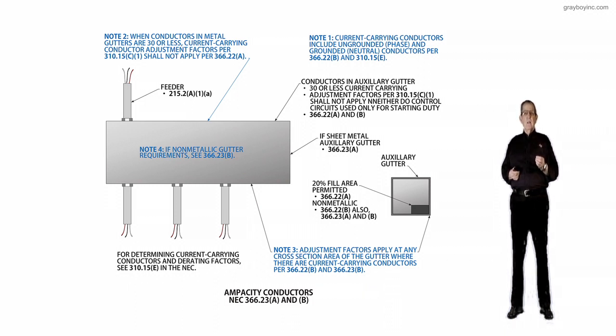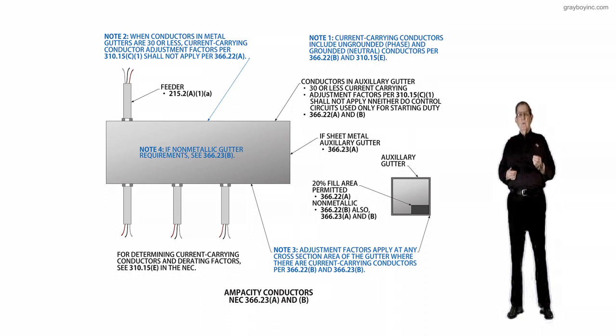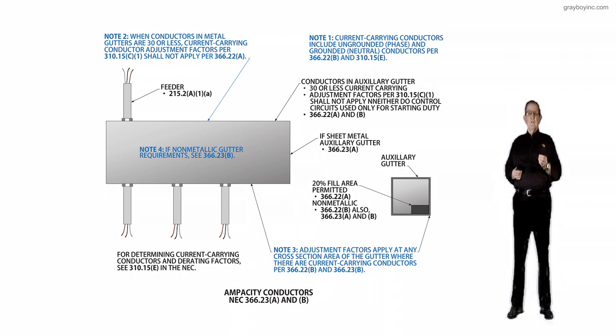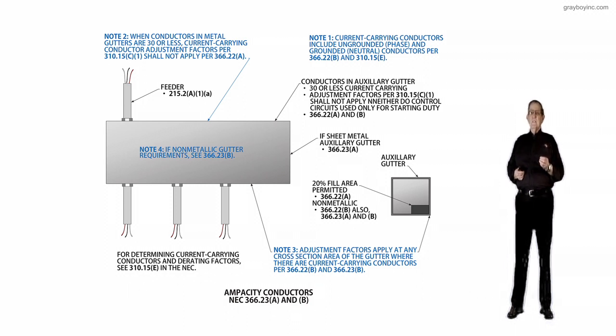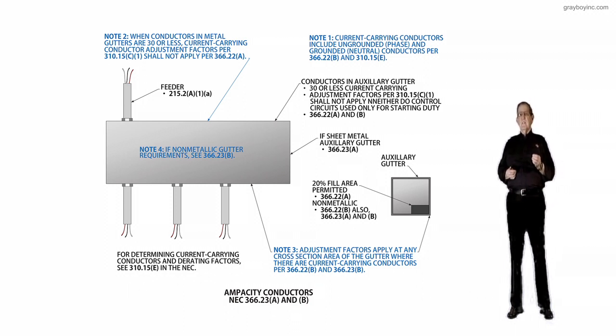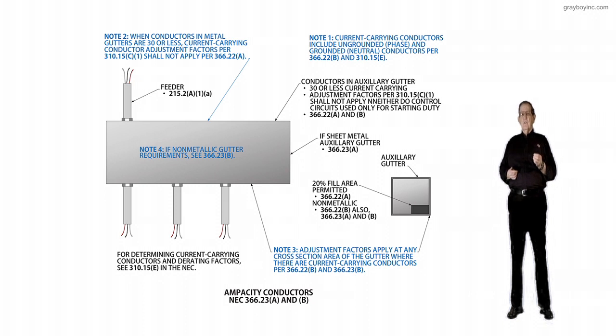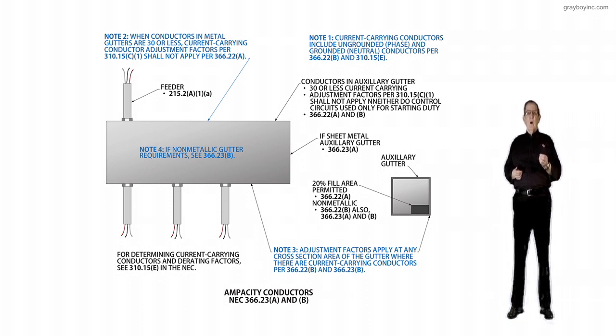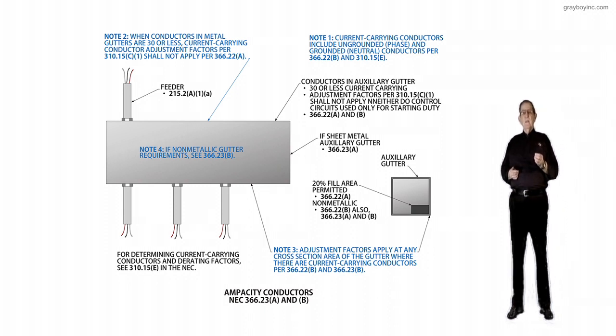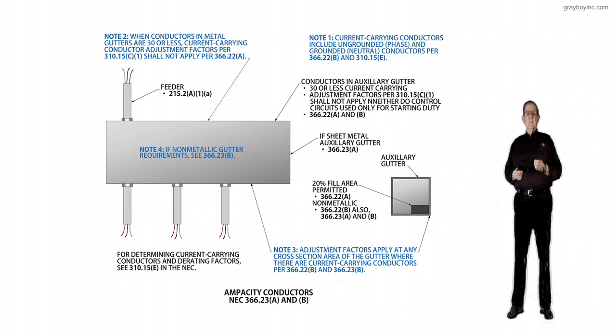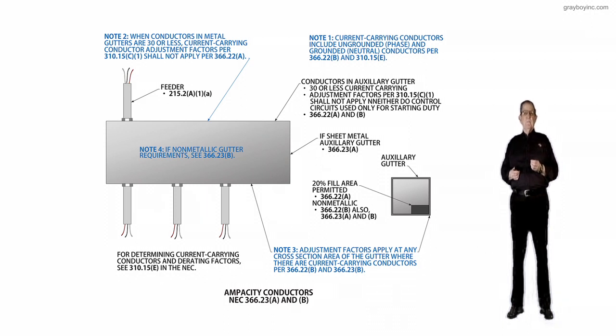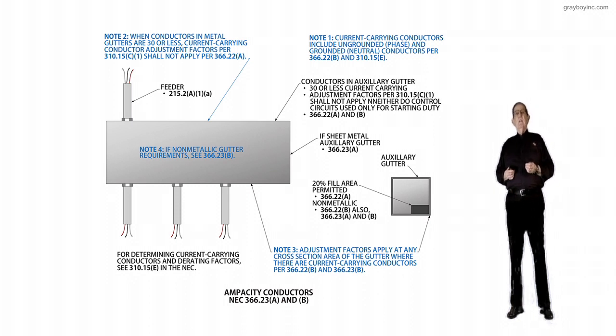...is incorporated to apply to conductors in a non-metallic auxiliary gutter and are applicable to the current carrying conductors up to and including 20% fill specified in 366.22B, which is consistent with the requirement of 378.22 for a metal wireway. Now, looking at the illustration...